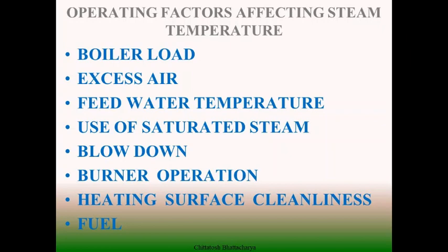So naturally it depends upon the boiler loading and how the combustion is getting controlled with excess air, because whatever combustion product is there within the boiler is carrying the heat, and if it is diluted with excess air, the dry flue gas loss increases.